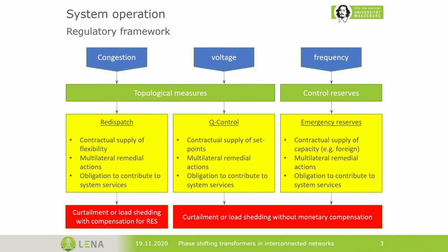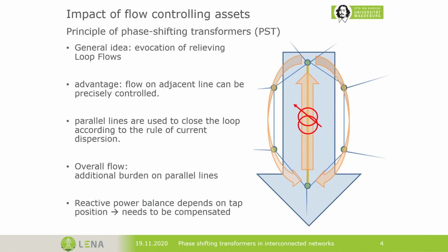So our phase-shifting transformer would be located in the green box. So this is a topological measure, which means it's non-costly for the grid operator, and therefore it has to be used in a very early stage of the congestion. In Germany, we have two main paths for congestions. One is north to south, and one is west to east. And here you can see the north to south main flow as the blue arrow.